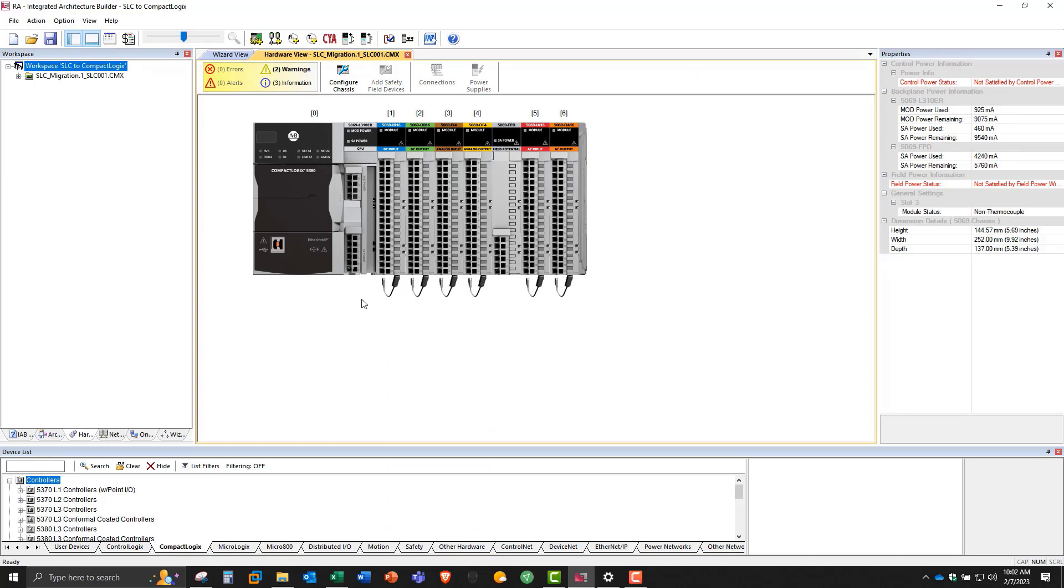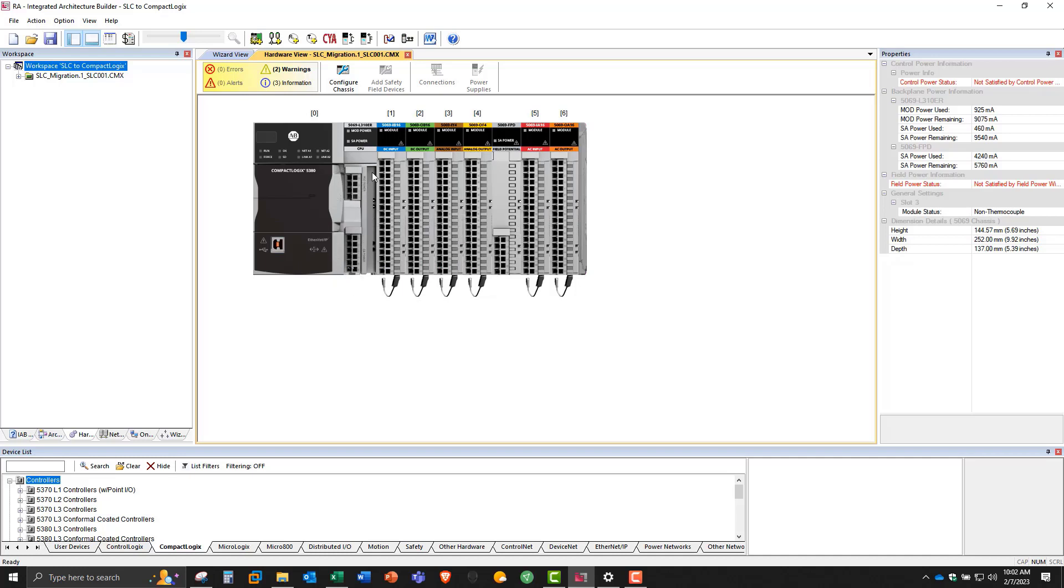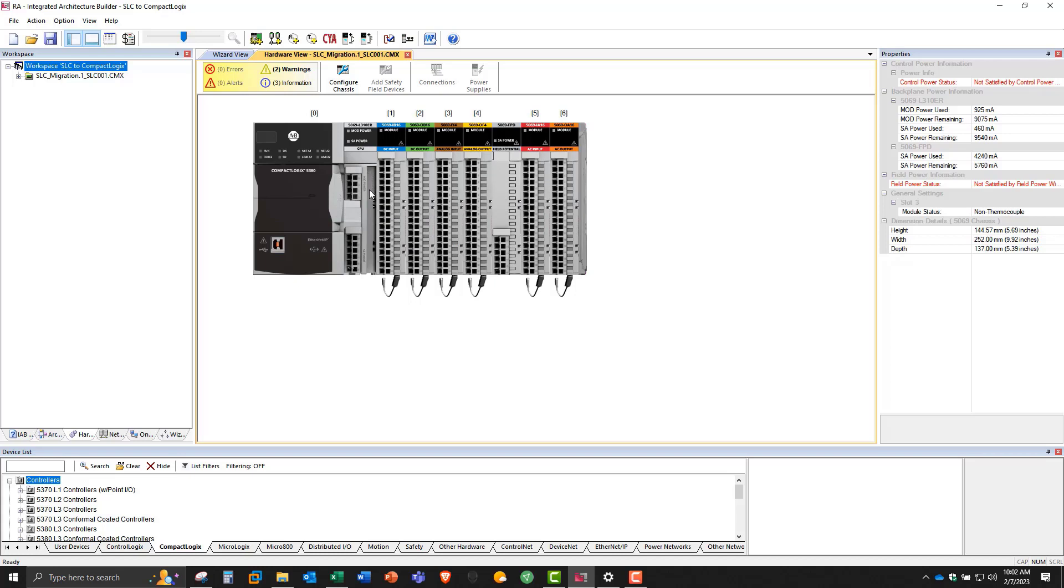Now, one thing to keep in mind is the 5380 CompactLogix requires 24 volts to power it. And you can see there's two terminal blocks. One up here is called the MOD power terminal block, and down here is called the SA power block. MOD stands for module, and SA is sensor actuator. You can see over here on the right, control power status and field power status aren't satisfied. So let's add some power supplies for this.